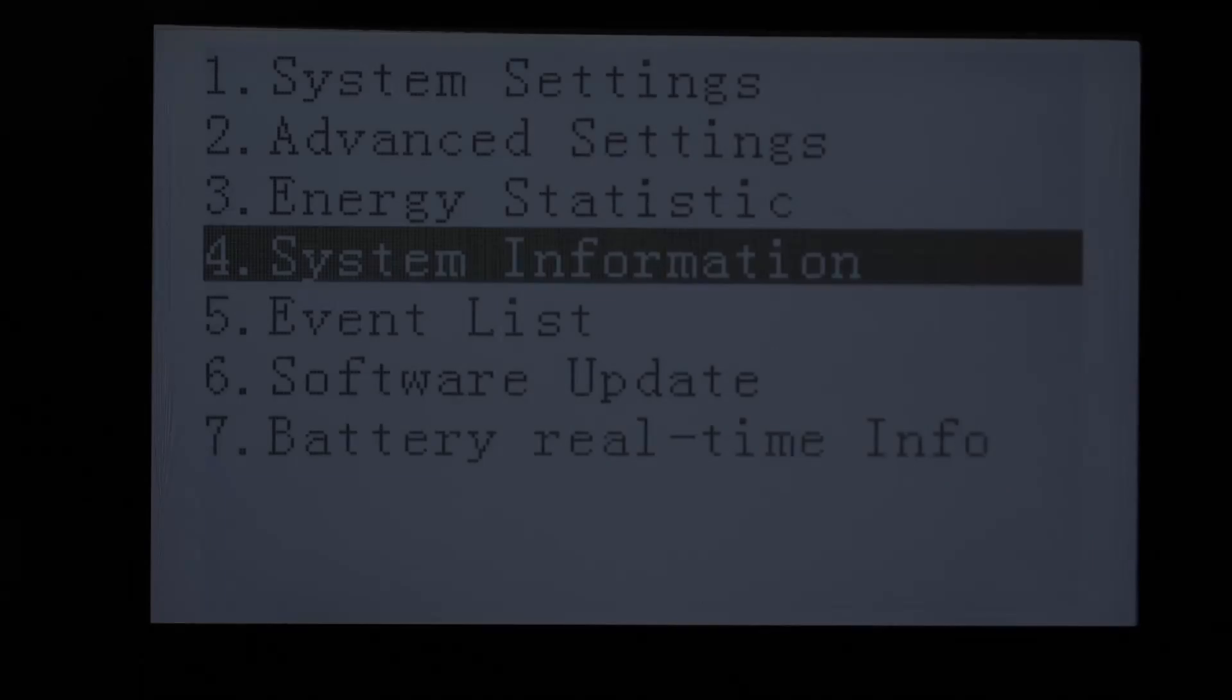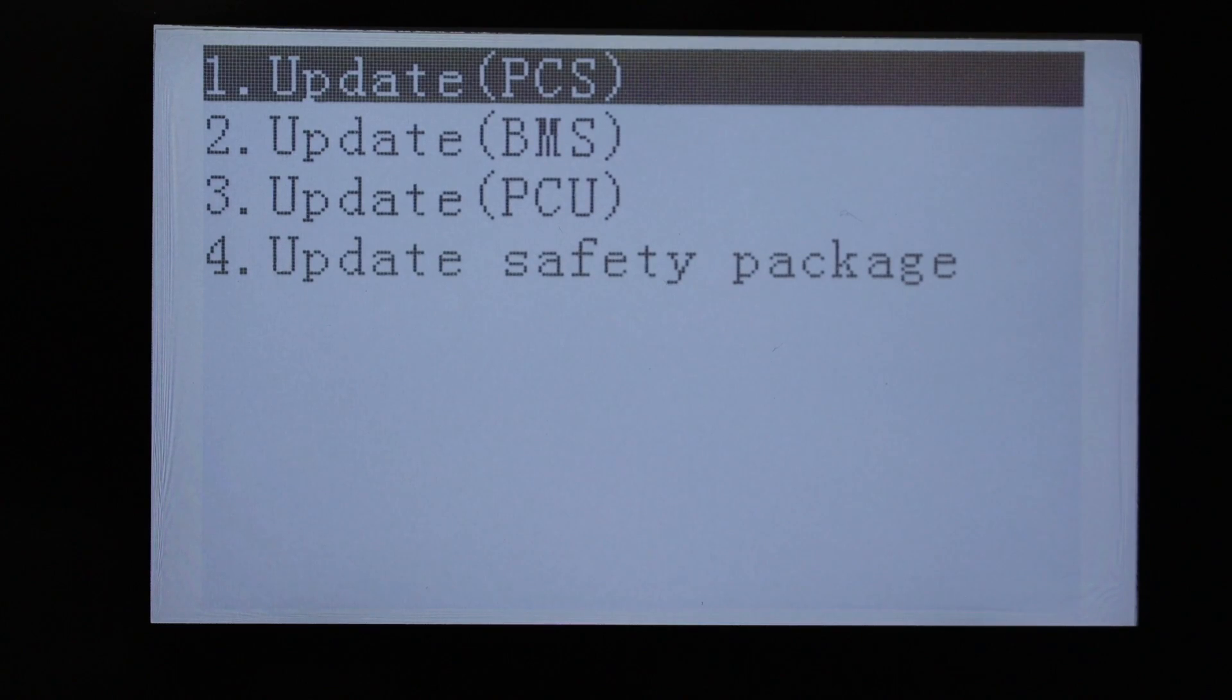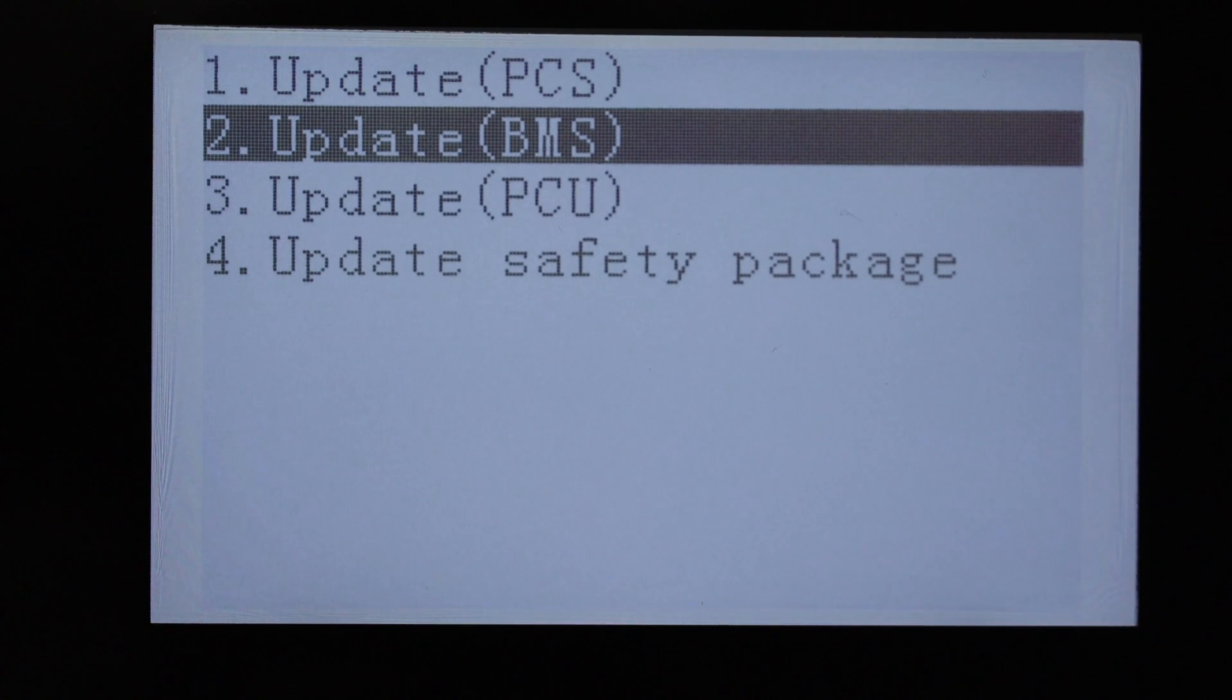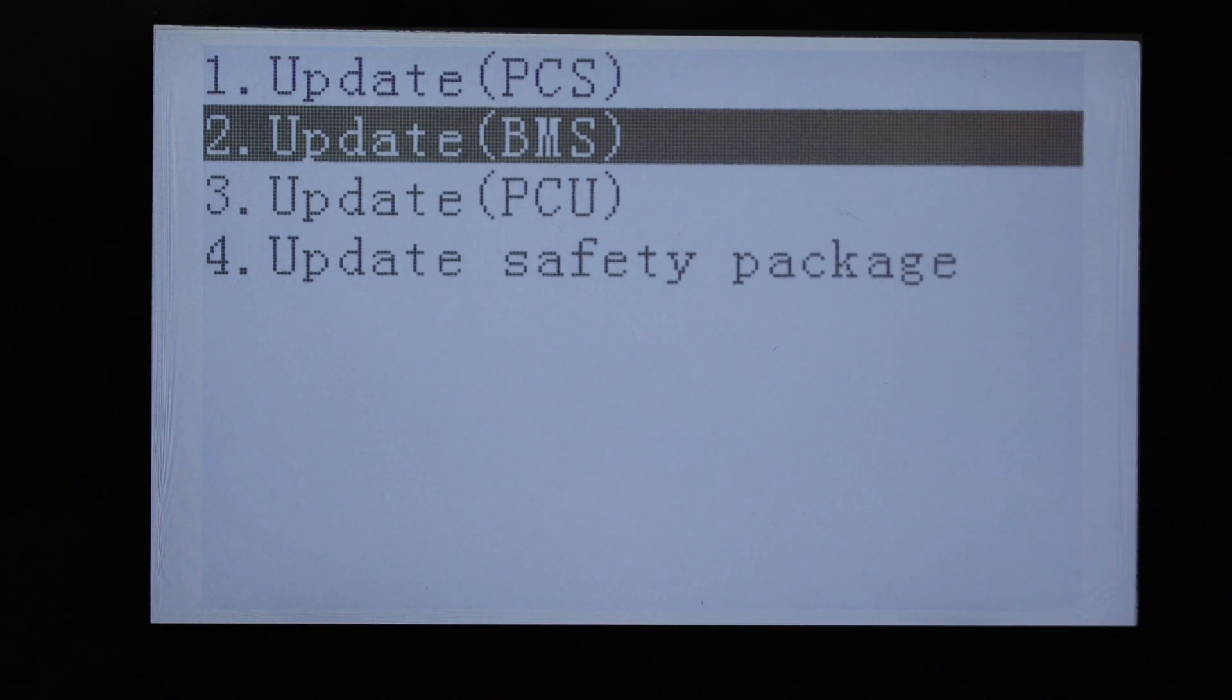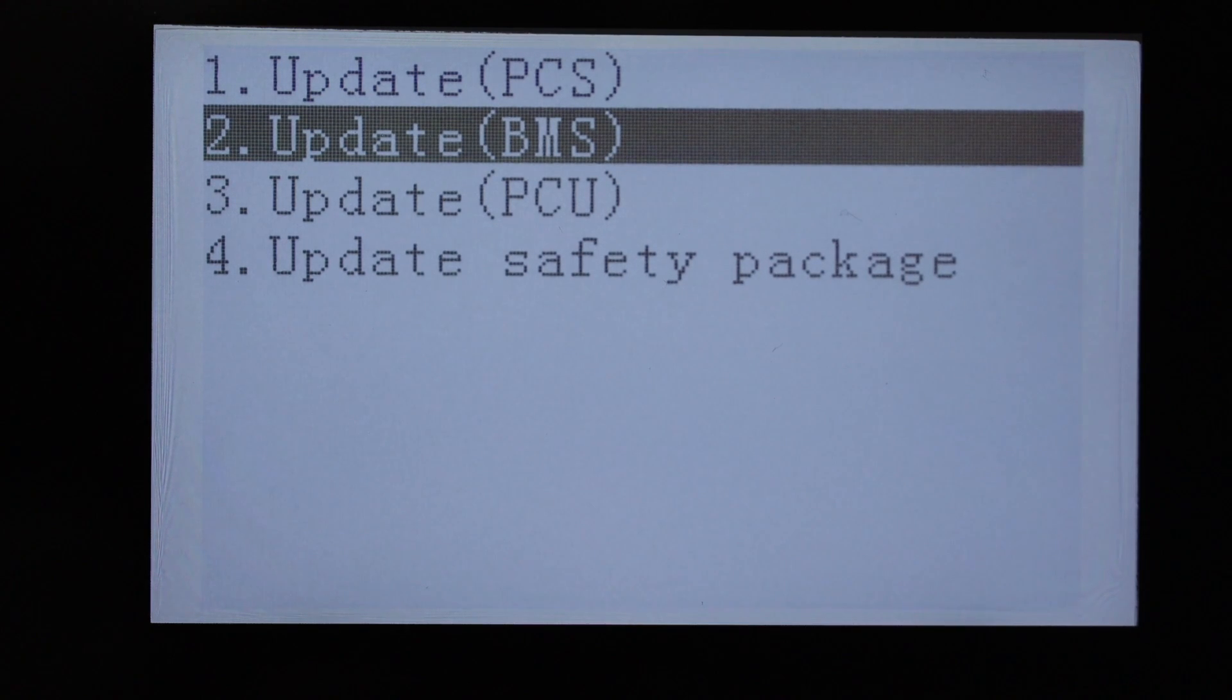Now we're going to upgrade battery firmware. Going into the system, upgrades. First bit will be the BMS. We need to make sure that you have two power sources. It can be either battery and DC, or battery and AC. In my case it's battery and AC. Now I'm going to carry out BMS upgrade.